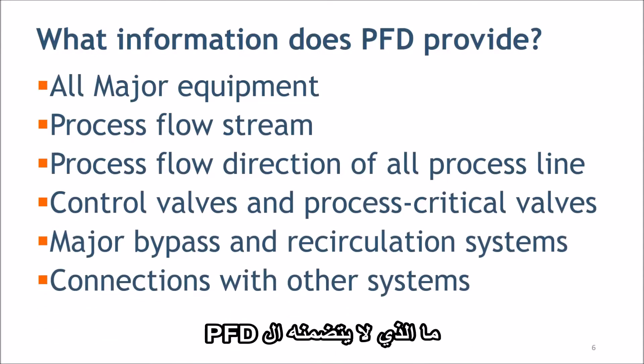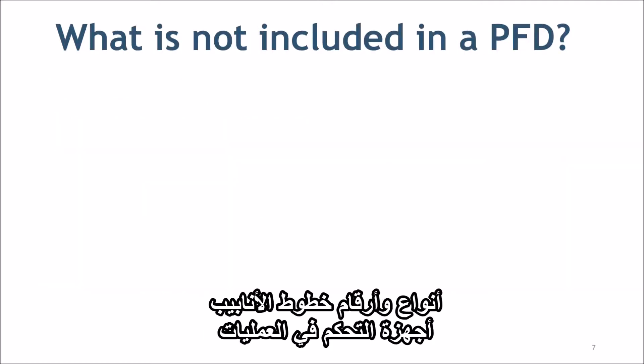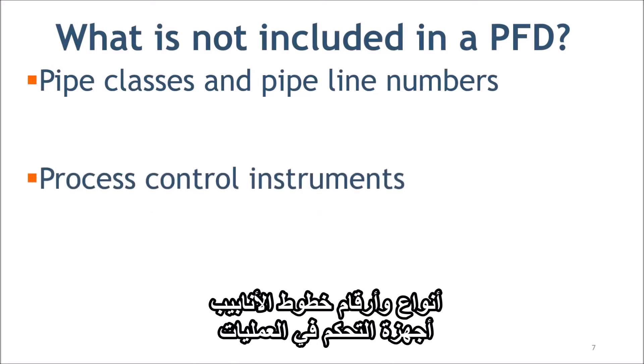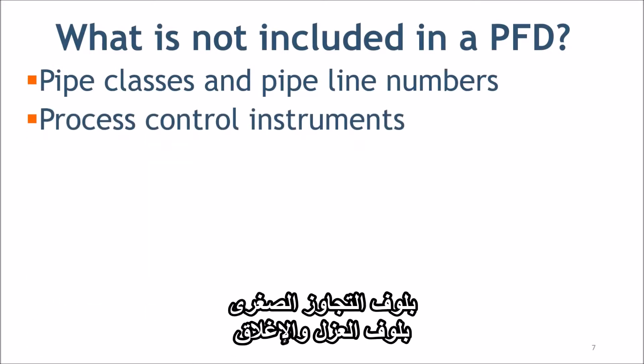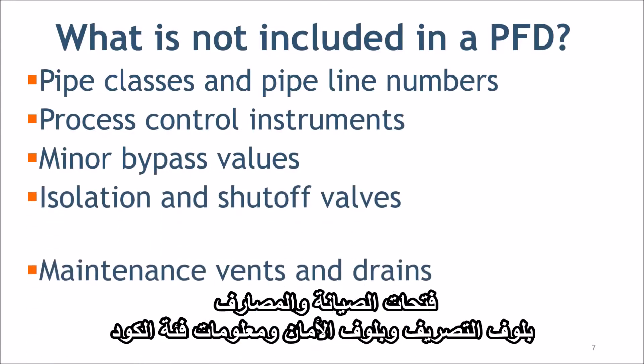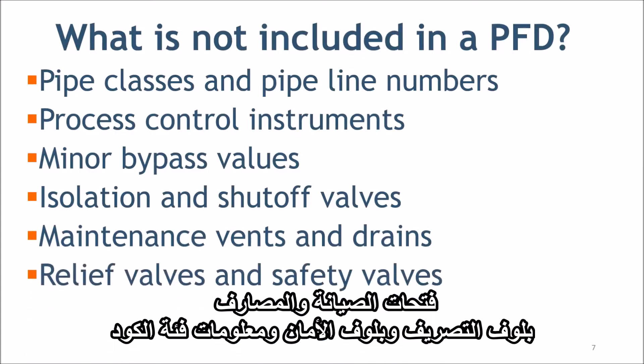What is not included in PFD? Pipe class and pipeline numbers, process control instruments, minor bypass valves, isolation and shut-off valves, maintenance vents and drains, relief valves and safety valves, and code class information are not included.